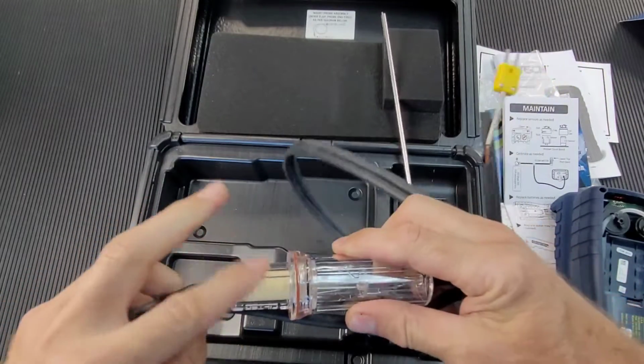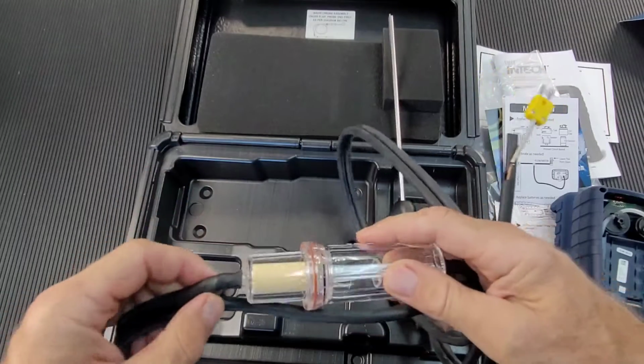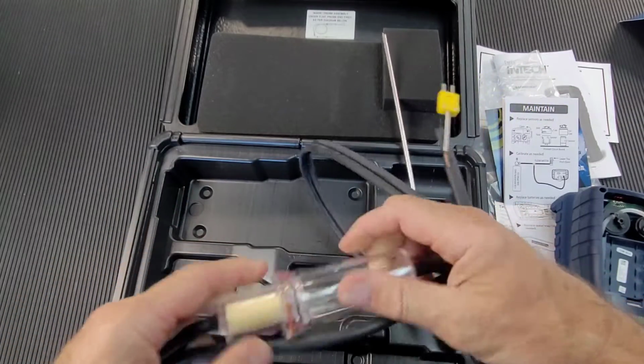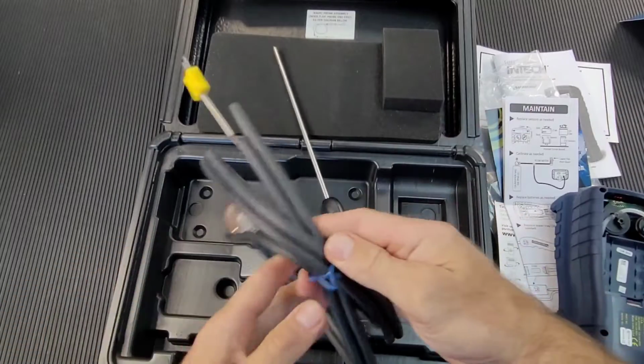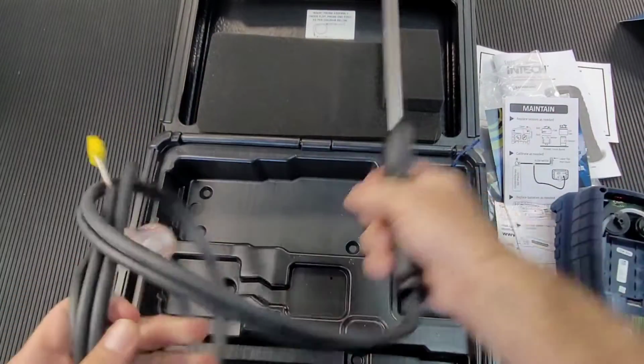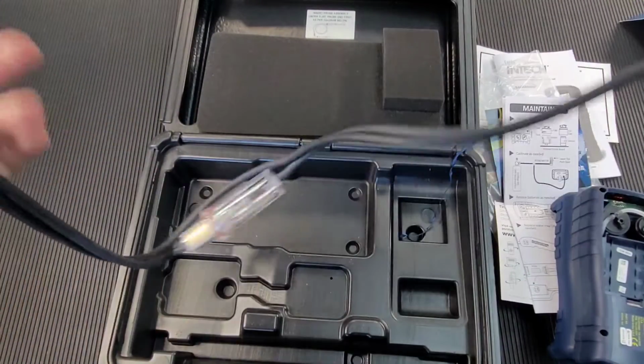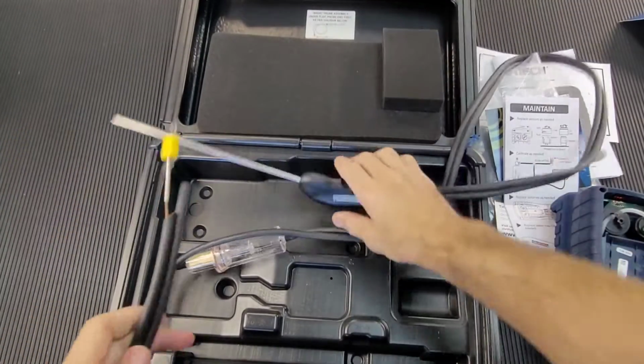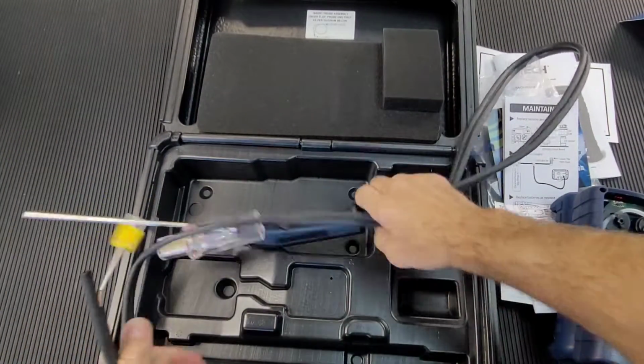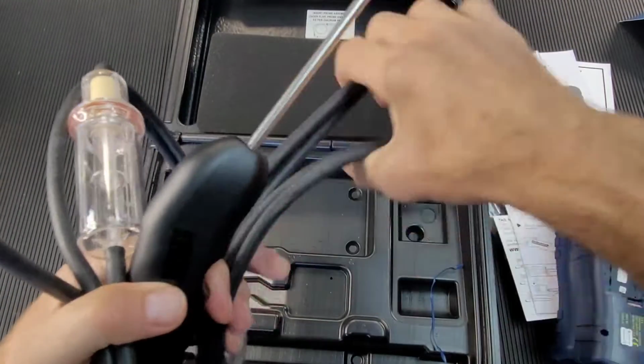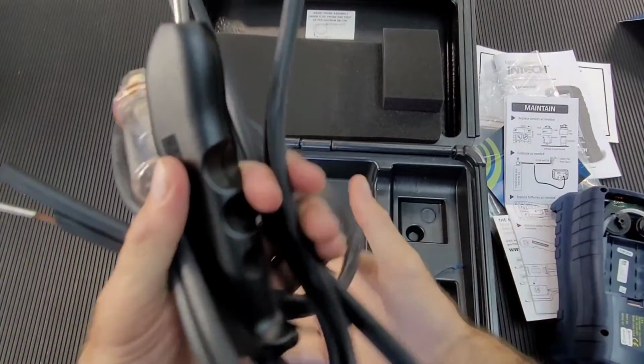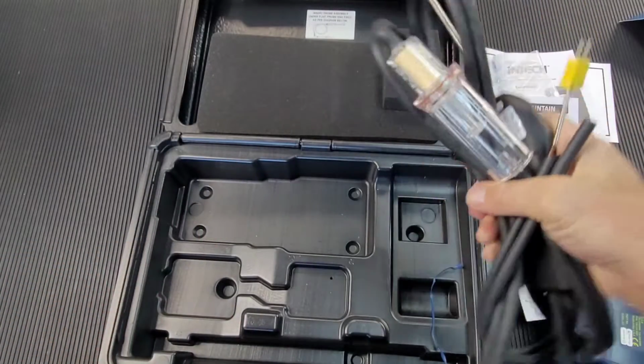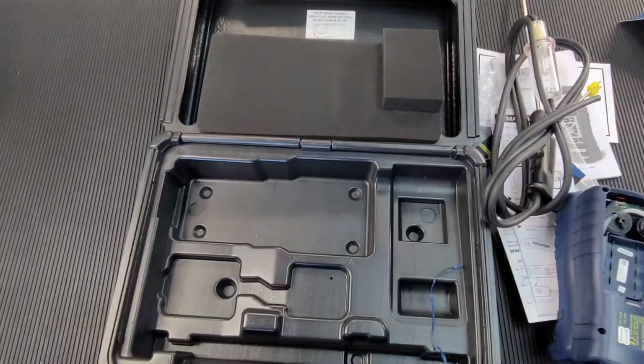So we have got the water trap and the particulate filter there, and this is quite a nice system. It is quite bulky, and that's again from personal use of this for years. It's just on the heavy side and the lengthy side, but nevertheless, it is what it is, and it has stood up the test of time, and people do like them. It does its job quite well, but I would prefer the silicone tubing. That's my personal preference. Okay, let's put that on the side and crank him on.